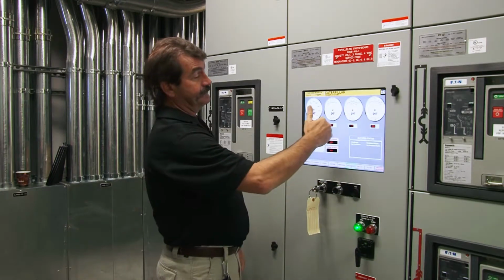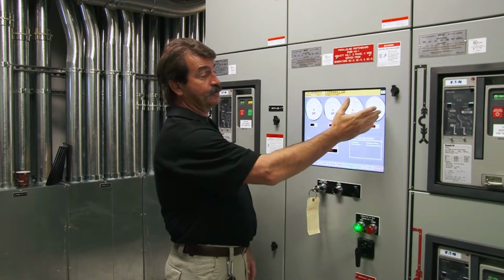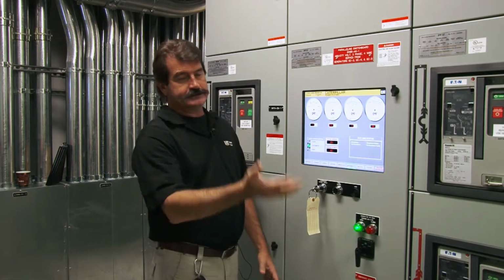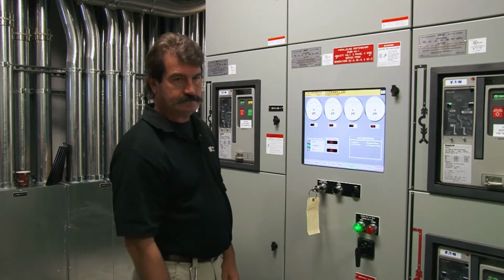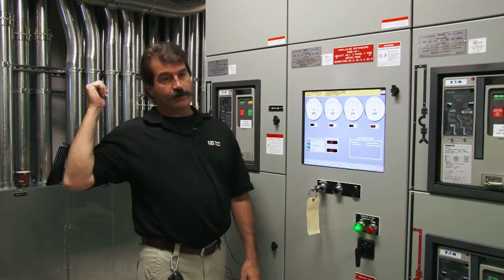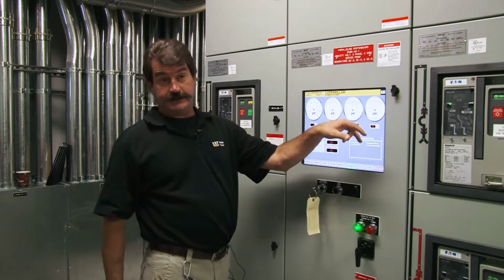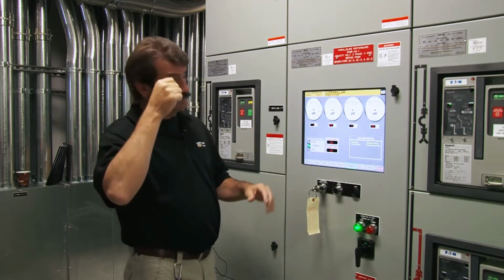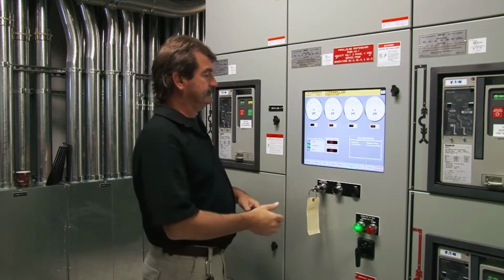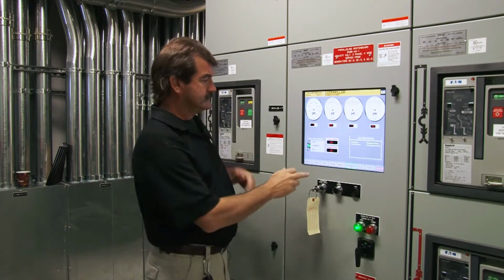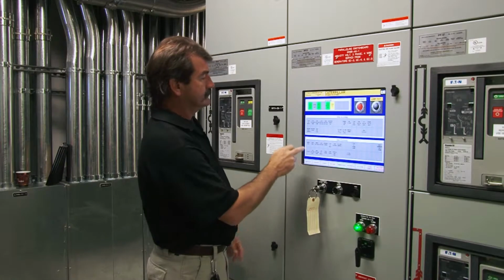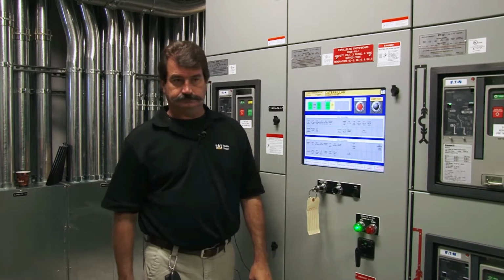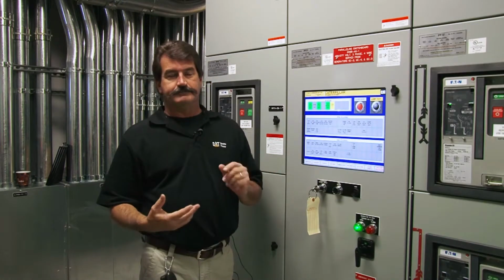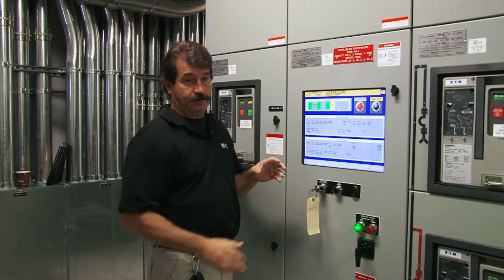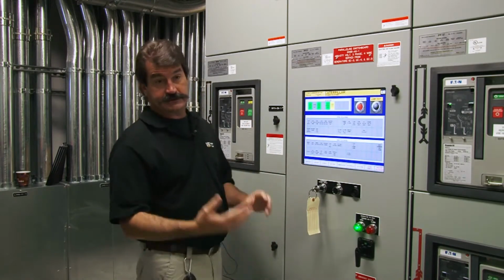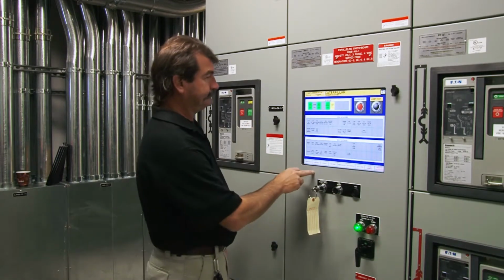Even if oil pressure stays low, or water jacket gets too high, low water jacket heater -- that'll alarm out there and send it into here. And you'll have a pre-alarm, low coolant temp right there. You'll have that, but it's just a pre-alarm, nothing that's going to keep you from running.